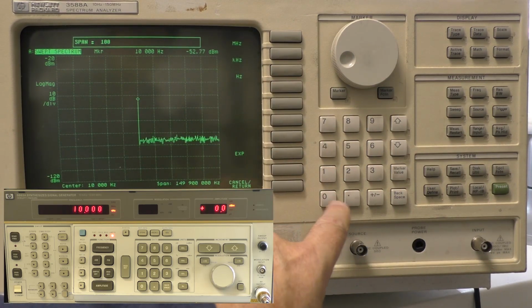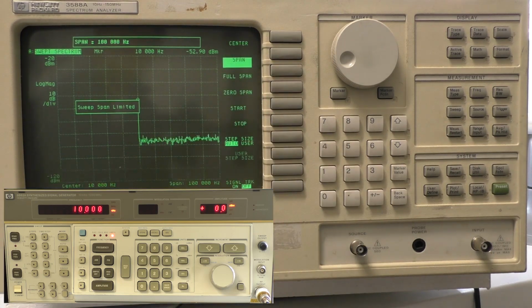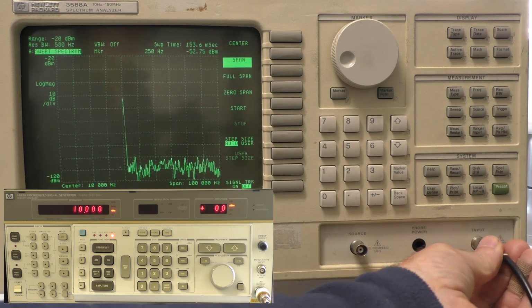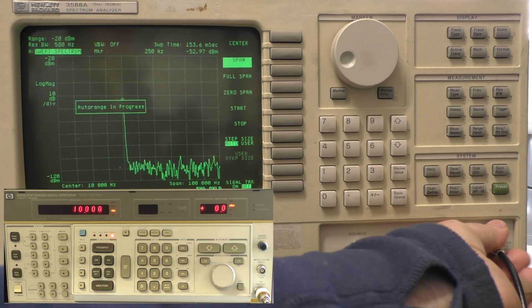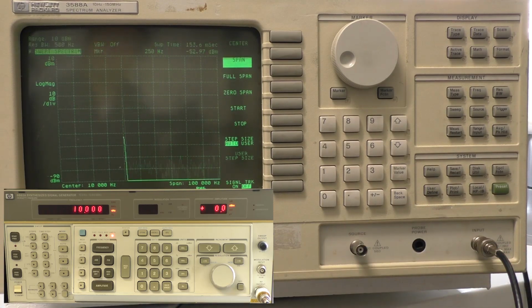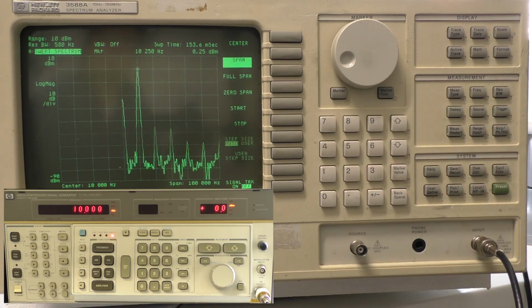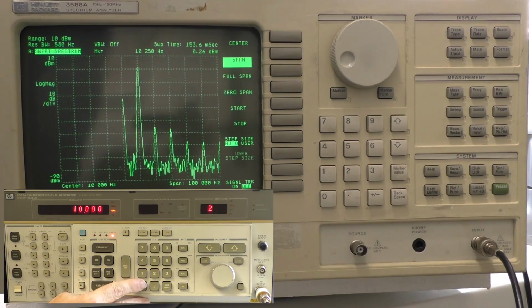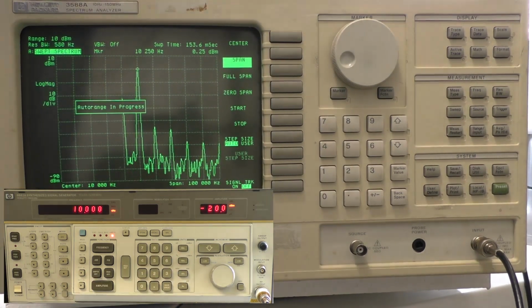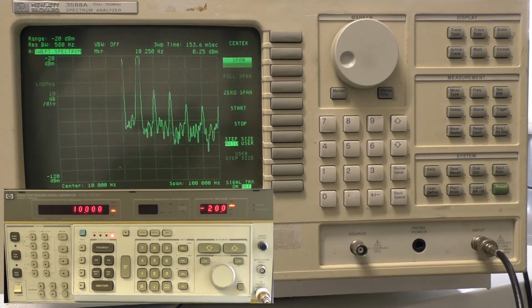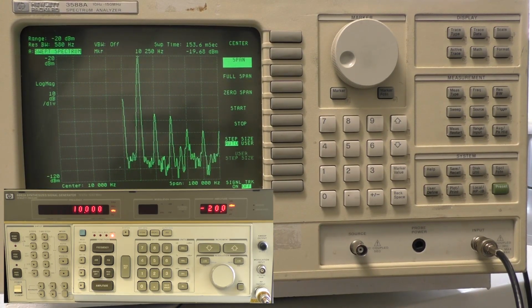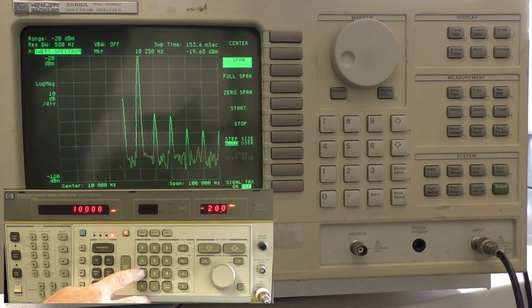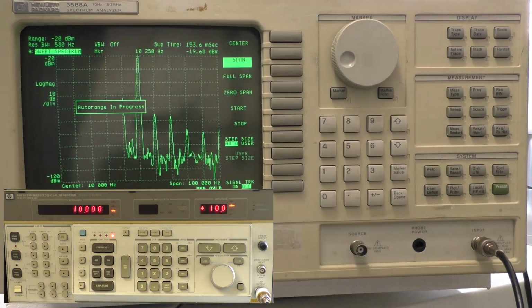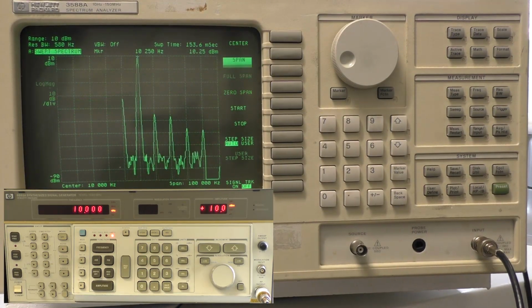With our signal generator set to 10 kHz and 0 dBm, plug the generator into the input. We see the auto range kicking in. The unit has detected the 10 kHz signal at 0.25 dBm, not bad. Set the signal generator to -20 dBm. The unit has detected the signal at -19.68 dBm, again not bad. Set the signal generator to +10 dBm. The unit has detected the signal at 10.25 dBm.